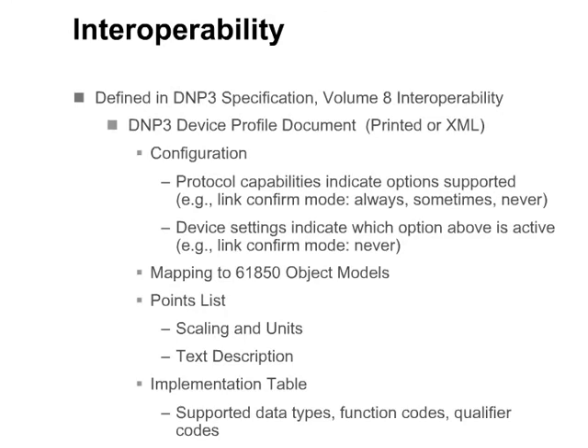Interoperability requirements are defined in Volume 8 of the DNP3 specification. Each device should have an associated DNP3 device profile document. This document has typically been provided in a printed format; however, going forward, devices should supply the document using the defined XML schema. An XSLT document is available to provide an HTML version of the device profile that is more human-readable and can be printed. The XML-based device profile document facilitates mapping the device configuration to IEC-61850 object models as well.